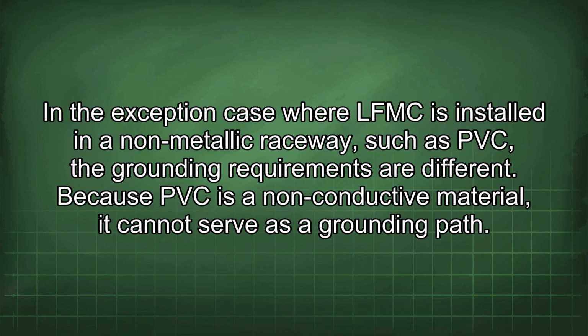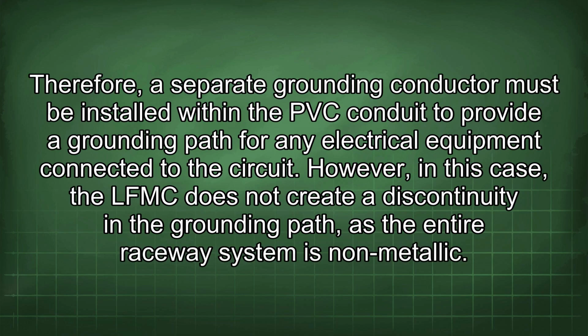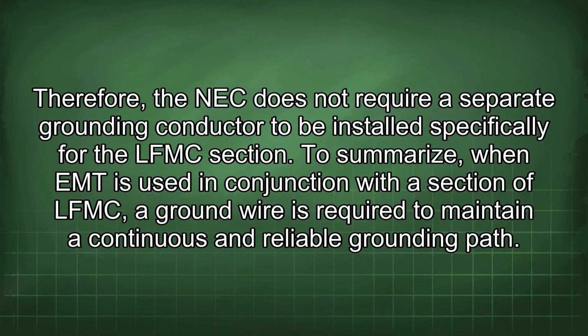In the exception case where LFMC is installed in a non-metallic raceway, such as PVC, the grounding requirements are different. Because PVC is a non-conductive material, it cannot serve as a grounding path. Therefore, a separate grounding conductor must be installed within the PVC conduit to provide a grounding path for any electrical equipment connected to the circuit. However, in this case, the LFMC does not create a discontinuity in the grounding path as the entire raceway system is non-metallic. Therefore, the NEC does not require a separate grounding conductor to be installed specifically for the LFMC section.